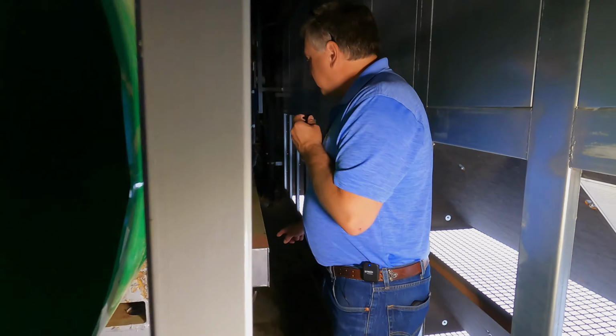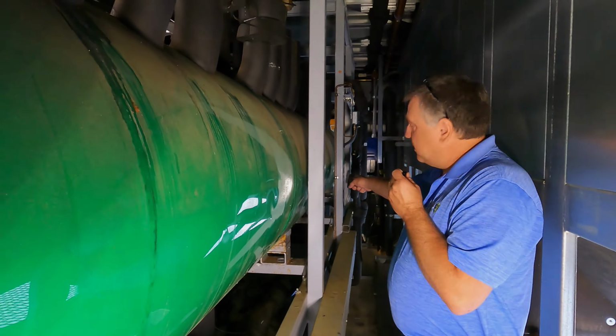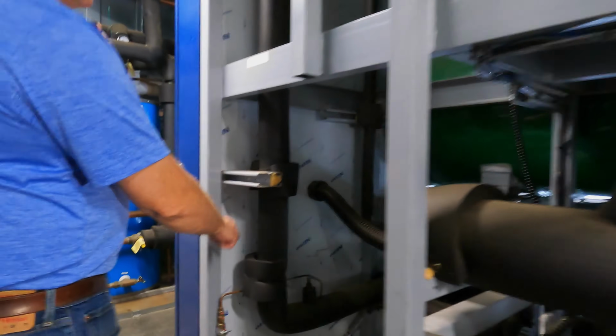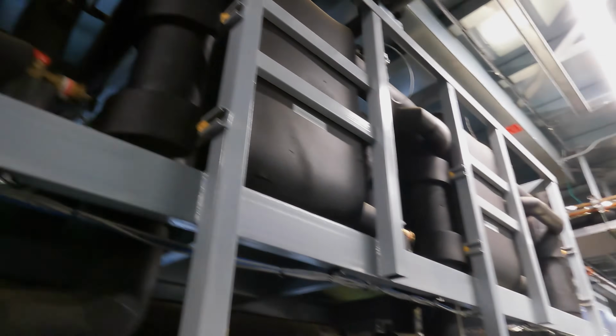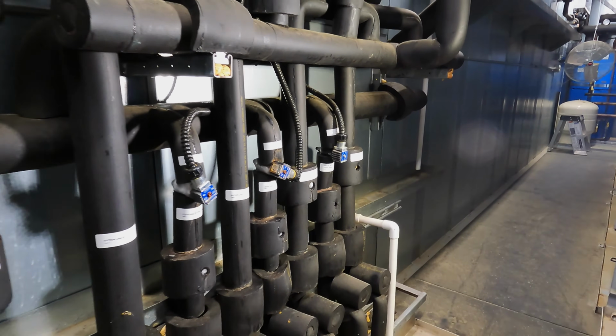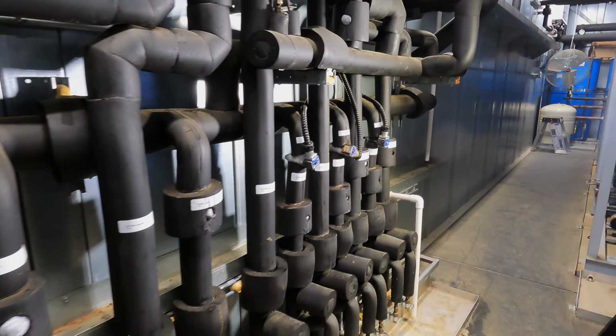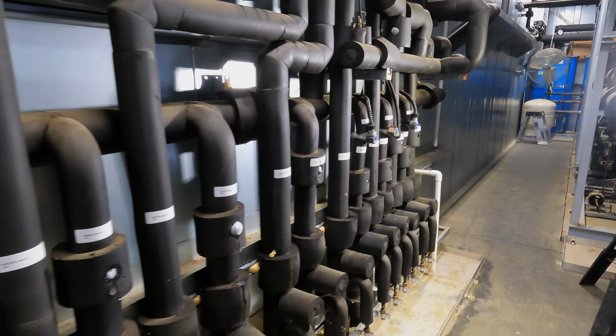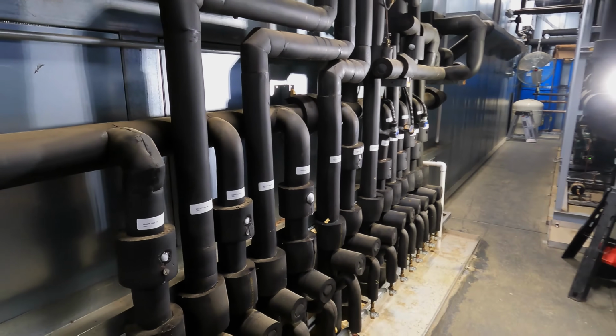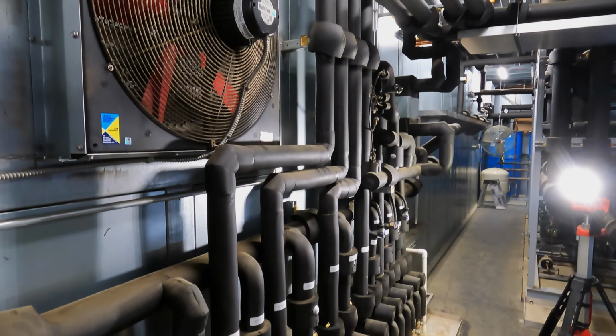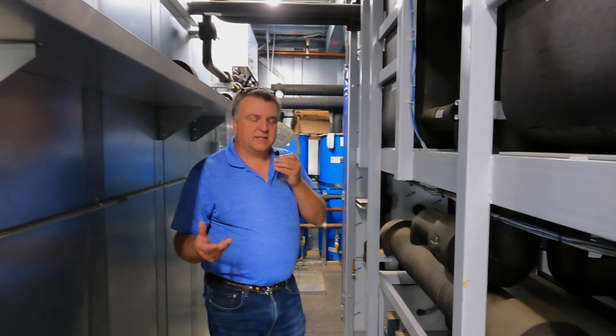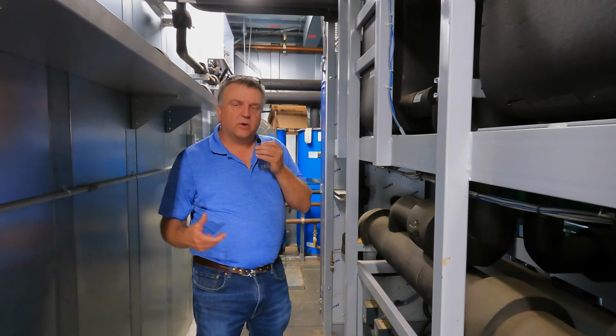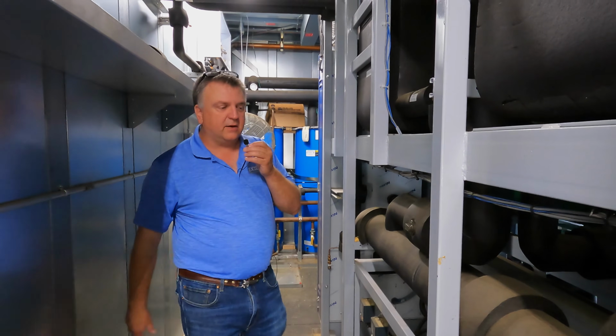For pumping CO2 liquid, it goes through a set of dryers. Our liquid CO2 comes out and over to our liquid header. All that piping goes downstairs into the store and circulates CO2. On the medium temp, all we have is liquid CO2 in and saturated vapor coming out. Very important that the CPC sensors inside the case are working properly because that's what's maintaining our temperature.